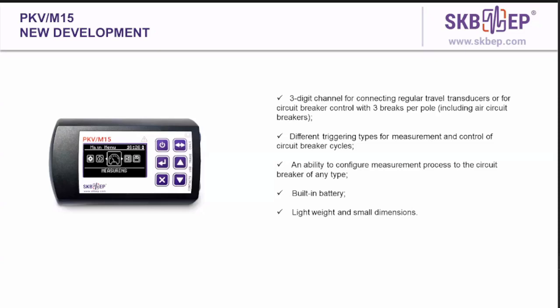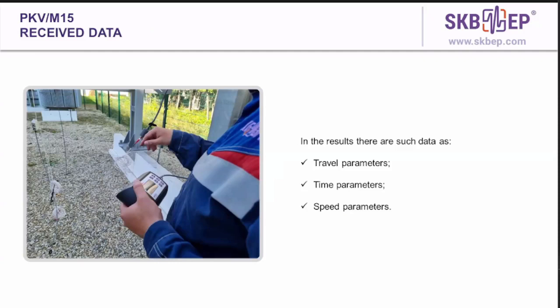The next is Circuit Breaker Analyzer PKV M15. It's our newly developed device. It has 3 discrete channels to control circuit breakers up to 220 kilovolt. It is aimed mainly at circuit breakers from 6 up to 35 kilovolt. There are different triggering types, which can be used depending on the equipment or on the conditions. For example, there is a dry contact triggering or main contacts closing triggering. Also, there is a built-in battery that makes its usage convenient and easy, and it has a compact ergonomic case. Here you can see in the picture the guy holding the instrument itself. It's pretty small. Despite its small size, the device performs all necessary measurements for circuit breaker diagnostics and receives time, travel, and speed parameters.